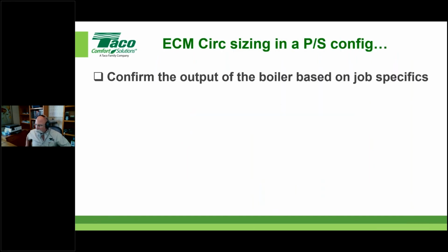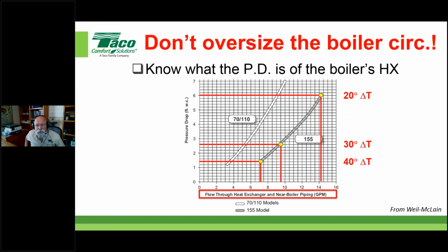So Rick, let me just clarify. You're saying that the boiler pump for a 155,000 BTU ModCon boiler, if my design delta T across that boiler's heat exchanger is 40 degrees, that boiler pump only has to be able to provide a shade over 7 gallons a minute at a little bit less than 1.5 feet of head pressure differential. Is that what that's saying? That's what that's saying. And you've got to always remember this, and only at a design condition. Okay. We can see how really easy it is to oversize a boiler pump now, to the point where it is now to the detriment of that boiler's operation. Absolutely.